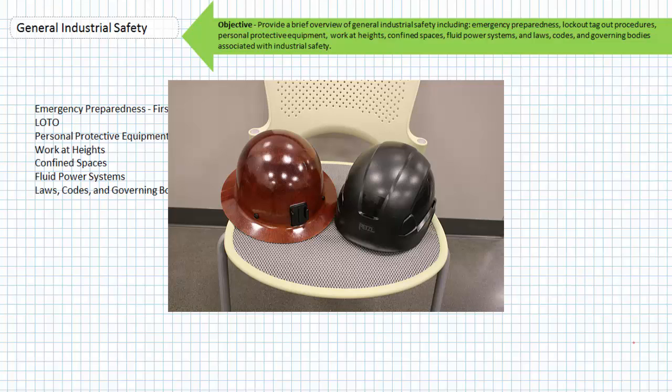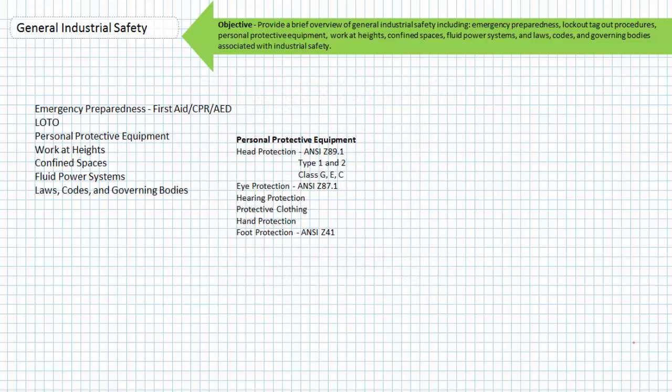Type 2 hard hats, noted by a brim around the perimeter, also protect against impacts to the side of the head. Hard hats are differentiated by three different classes: G, E, and C. A general or G class hard hat can protect up to 2,200 volts or 2.2 kilovolts.